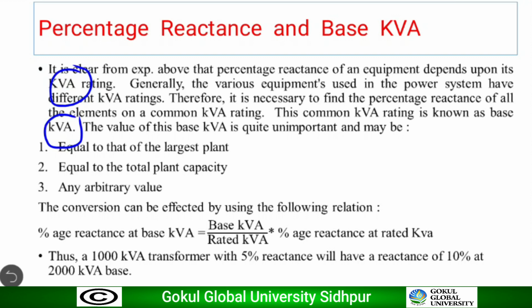So percentage reactance at base kVA is equal to base kVA upon rated kVA into percentage reactance at rated kVA.